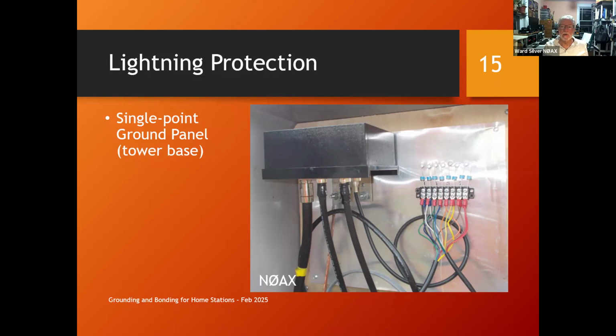So at the bottom of each of my three 60-foot towers, I have a single point ground panel at the tower base. It's a surplus fiberglass electrical box with a piece of plywood inside, and some basic aluminum flashing—the kind you get at the store in a roll, 10 or 15 feet. I just use sheet metal screws to tie it to the plywood.